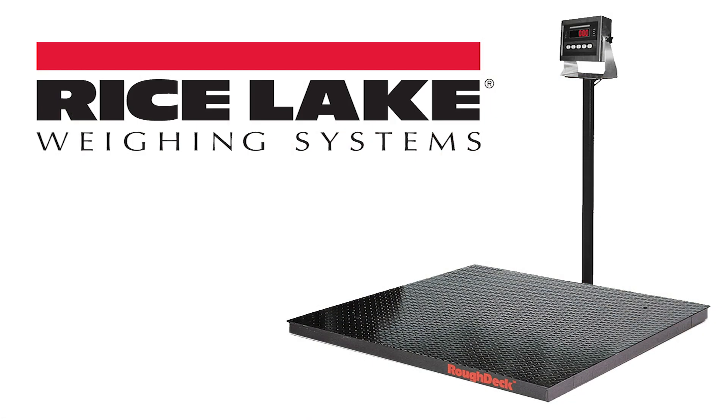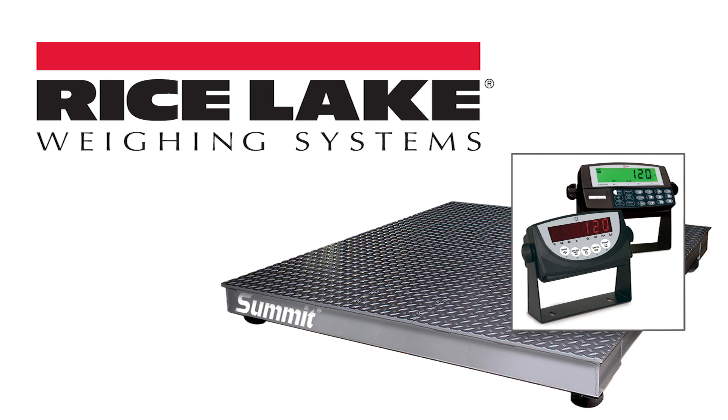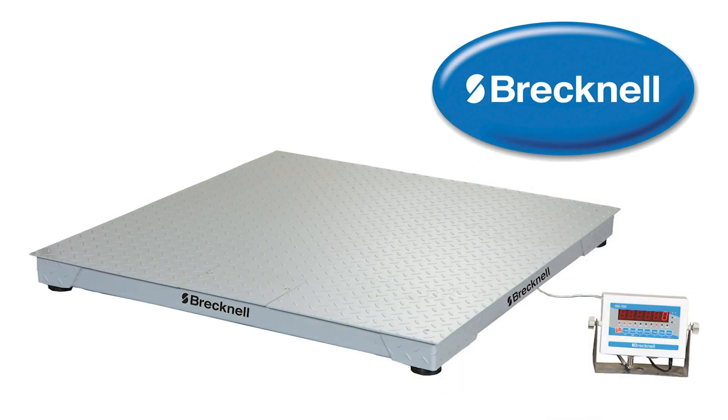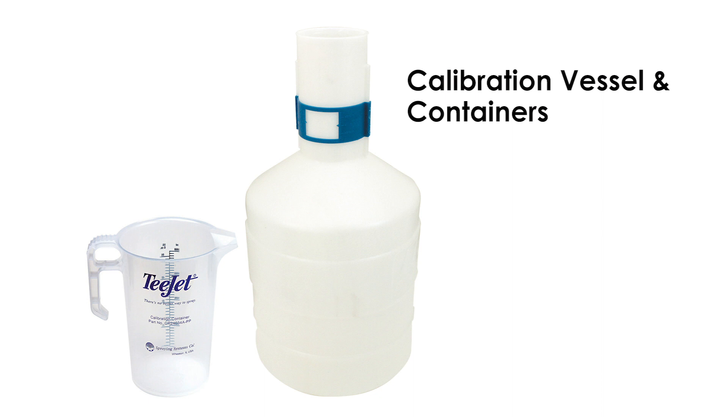This calibration procedure can also be completed using a legal-for-trade scale in place of the prover container. You will need to know the weight of the product per gallon to calculate the total weight to be caught. Always check your meter calibration against a prover or calibrated scale prior to using for the day.